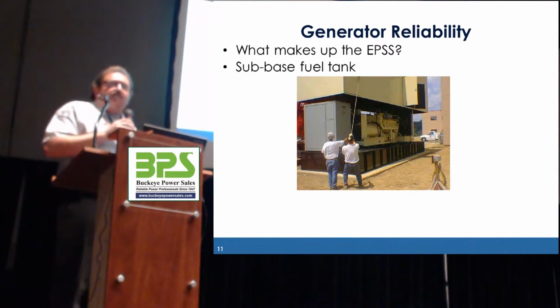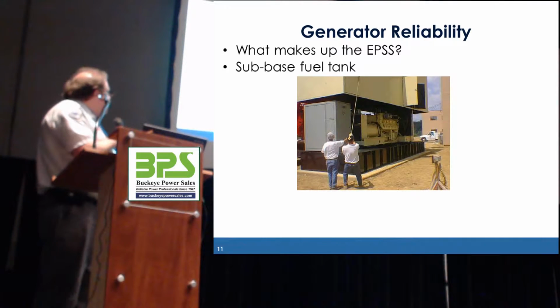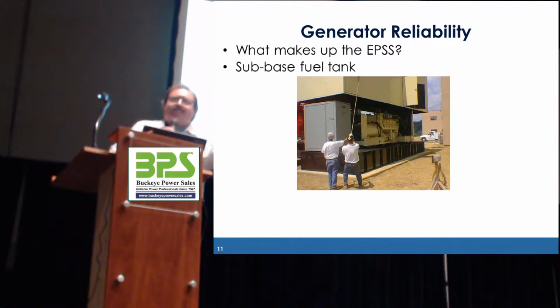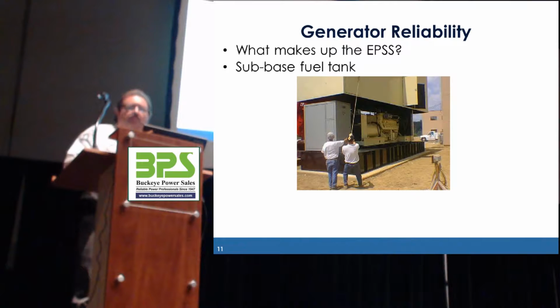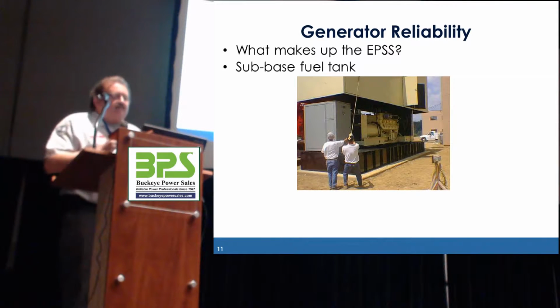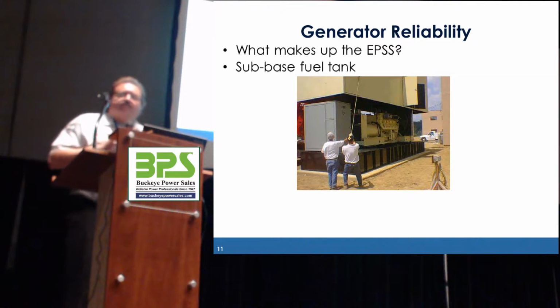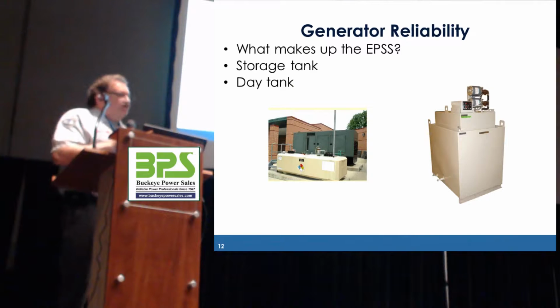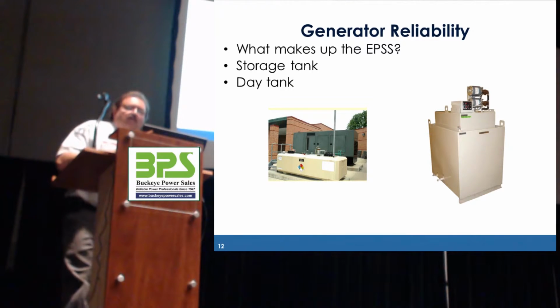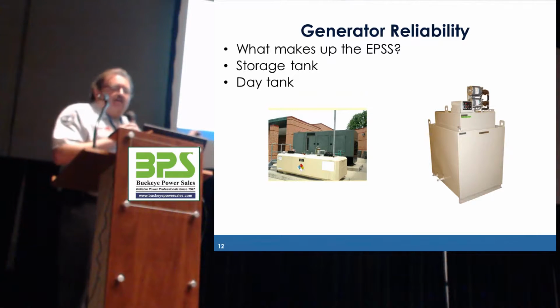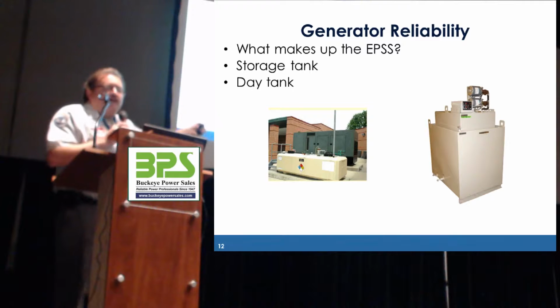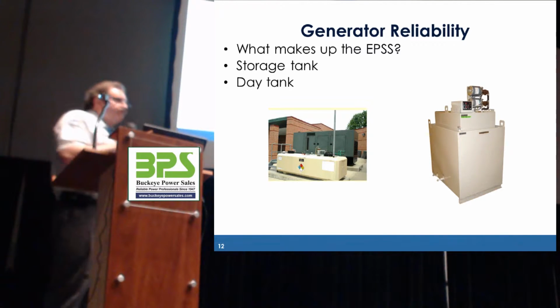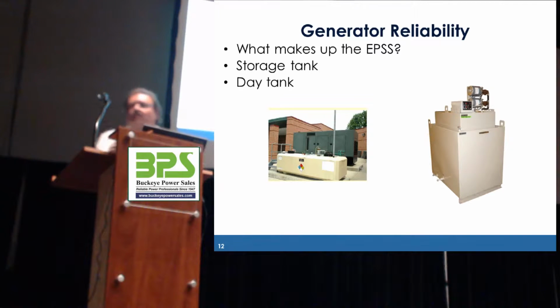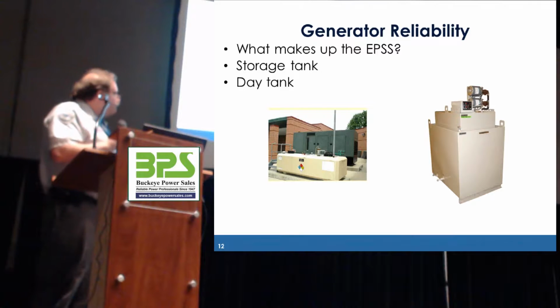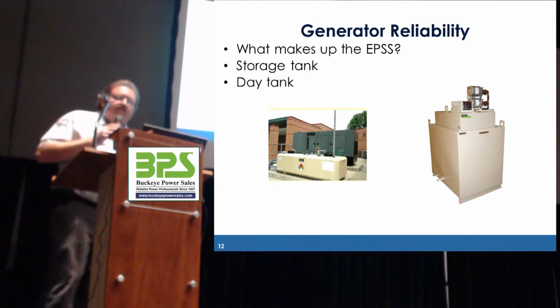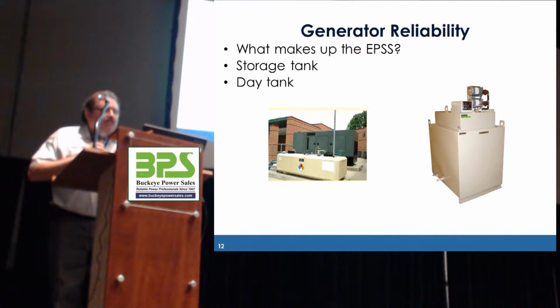Another part of it is the fuel system, right? So the fuel system can be made up simply as a sub-base fuel tank, like in the case of this generator where it sits on its own fuel tank. It's a single generator, it's big enough to run the entire facility, and it has, let's just say, a 24-hour fuel tank. But maybe for your facility, 24 hours at one time is insufficient, so you may need some sort of other storage tank, whether it be an underground, an above-ground convault, or any other type of tank, and then some sort of a day tank that draws that fuel from those other tanks and brings it to the machine so it can use that. Pretty straightforward. The other part is the load conductors, the cabling, and we'll talk a little bit more about that when we talk about infrared.